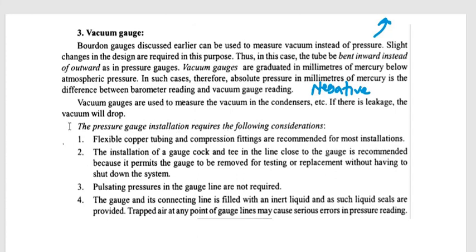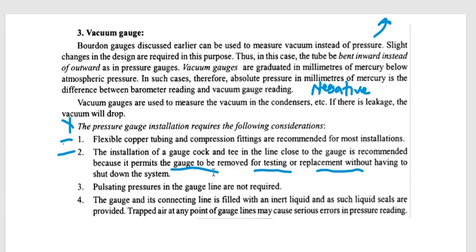The pressure gauge installation requires the following considerations: One, flexible copper tubing and compression fittings are recommended for most installations. Two, the installation of a gauge cock and tee in the line allows the pressure gauge to be removed for testing or replacement without having to shut down the system. Three, pulsating pressures in the gauge line should be managed. Four, the gauge pressure and its connecting line should be filled with an inert liquid; liquid seals should be provided, as trapped air at any point of the gauge lines may cause serious errors in the pressure reading.